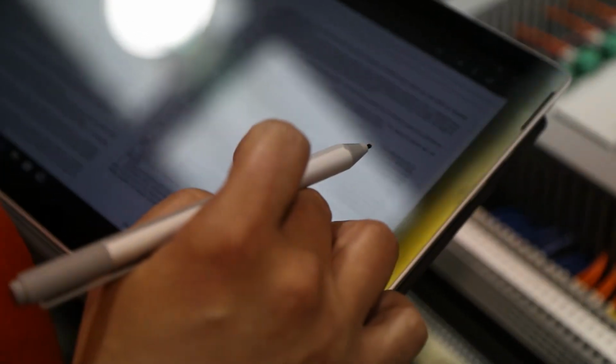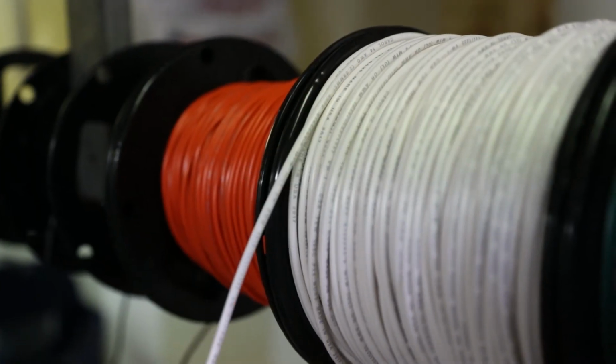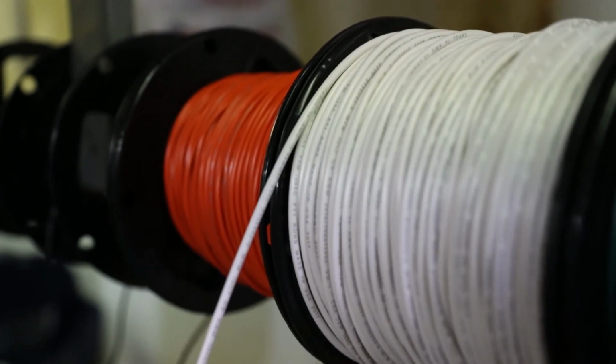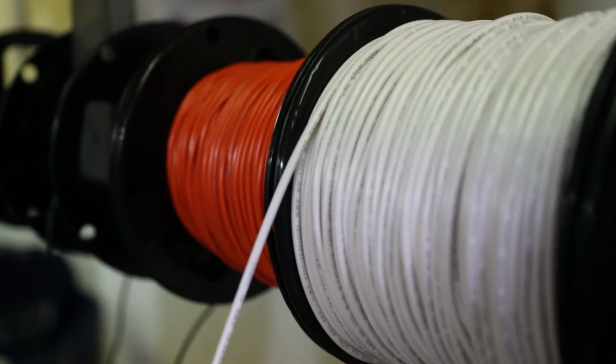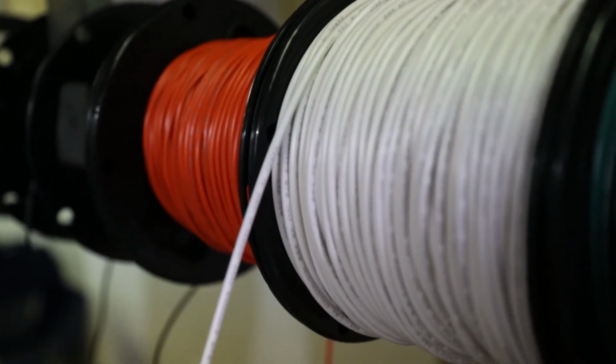So the age of a BAS is definitely going to factor into the problems you could run into. The equipment itself, the electronics starting to break down. They've been in service for 20 years or more. The cabling even starts to get brittle, so the insulation starts to break down. I've even seen where old cable apparently attracts squirrels. In one facility, they decided to get in there and start eating all the insulation off and subsequently bringing the network down. That was a very interesting one.